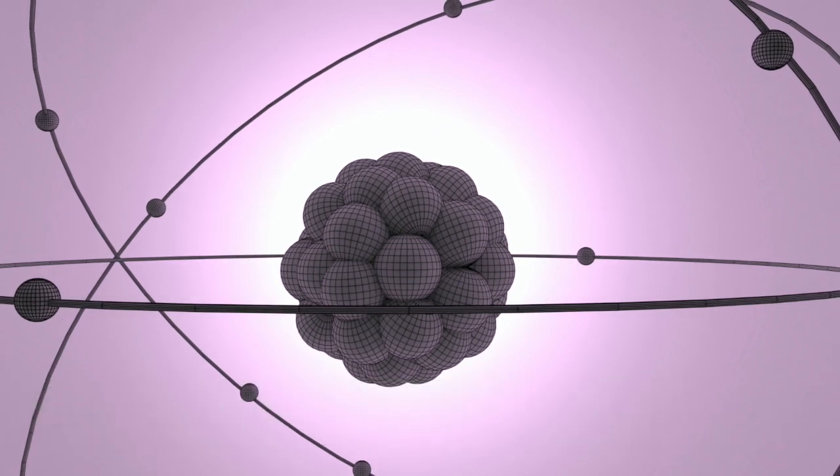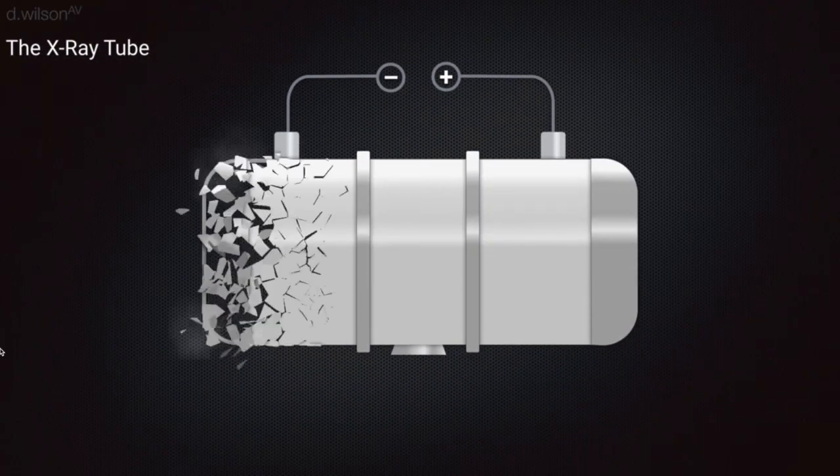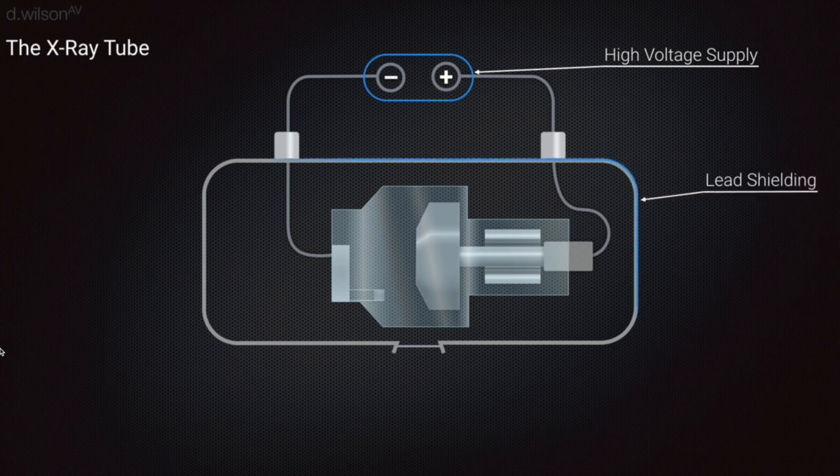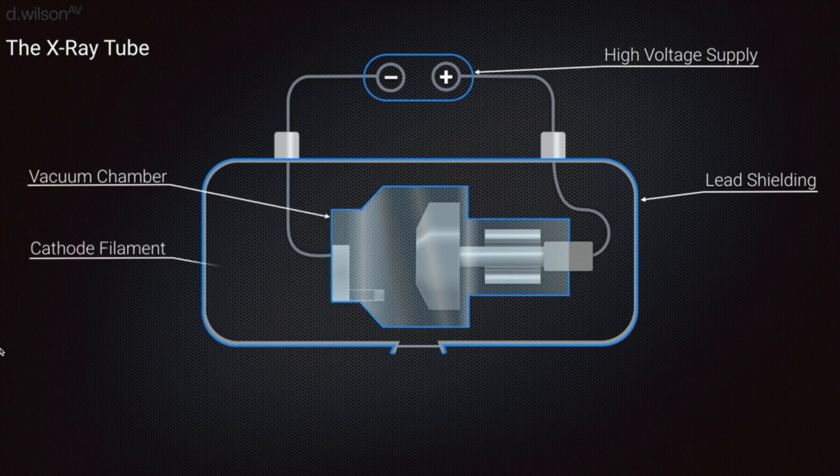In summary, X-rays are produced by three basic things: a source of electrons through thermionic emission, a means of accelerating electrons, and a method of decelerating these same electrons. The mA is used to control the number of X-rays, and the kVp controls the energy of those X-rays.